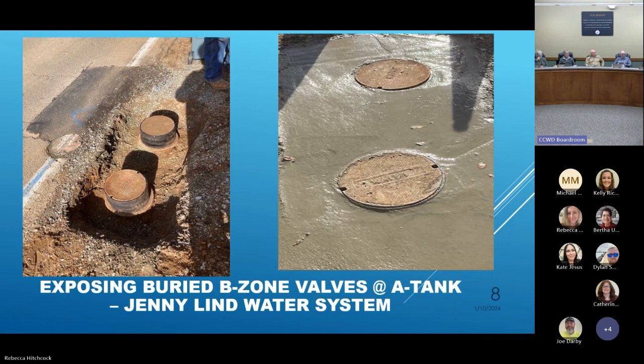Anecdotally, related to valves and effective operation and valve seating, we were talking about the seat of a fire hydrant earlier in the week out in the field in Rancho, I want to say on the end of Cassidy. We think the seat of that fire hydrant, at install or due to some past flushing of the system, had small pebbles and rocks shoved into the resilient seat. So as you shut it down, if you have a little water creeping by, you end up shutting it down even more.